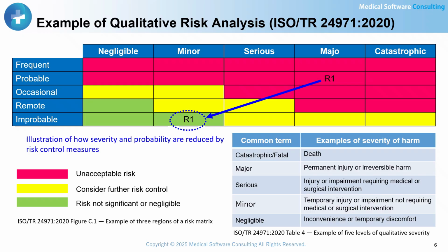If a manufacturer determines that a particular risk is unacceptable under the criteria established in the risk management plan, and if no further risk control is practical, then a benefit risk analysis may be performed. This analysis is used to determine whether the expected benefits of the medical device, for its intended use, outweigh the residual risks. It is important to note that benefit risk analysis cannot be used as a business decision tool. It cannot be about financial profit or economic gain outweighing risk. A simple analogy comes from the field of pharmaceuticals. Even when side effects exist, the therapeutic benefit of the drug may justify its use.